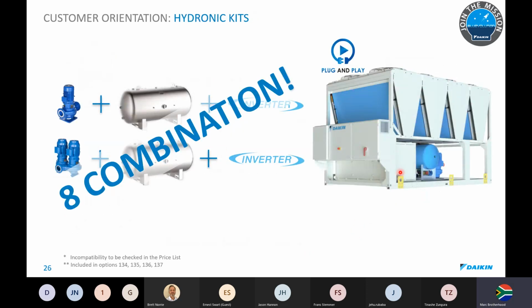Then these are the hydronic kits we offer here. You can see how we would put the storage vessel. This is pretty much what we call a buffer tank. The pump, single pump, dual pump. The chiller will come configured with a duty standby configuration to balance the run hours. There's 8 different combinations available. Plug and play, all the electronics are done for you. Just connect the water pipes. Like I said, expansion tank along with the buffer tank.